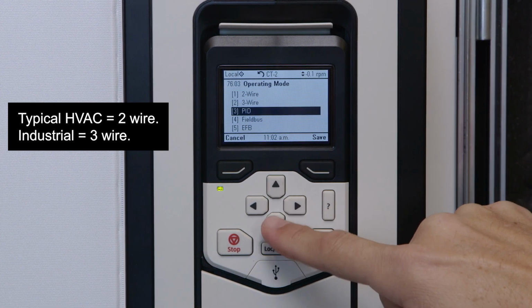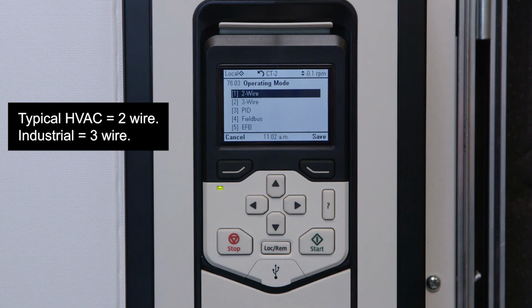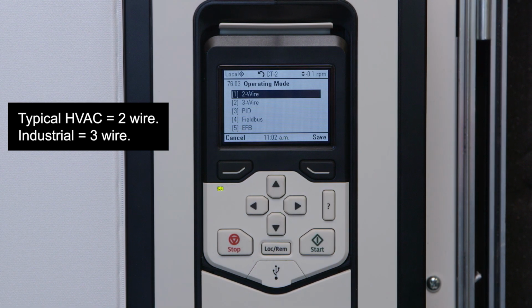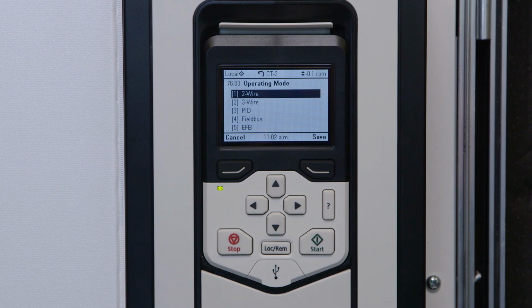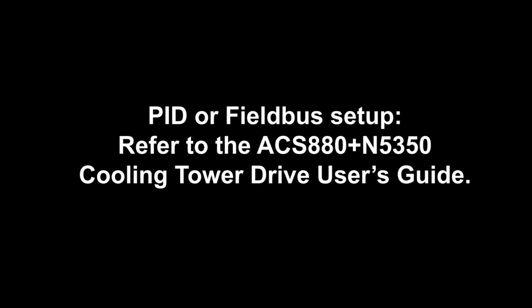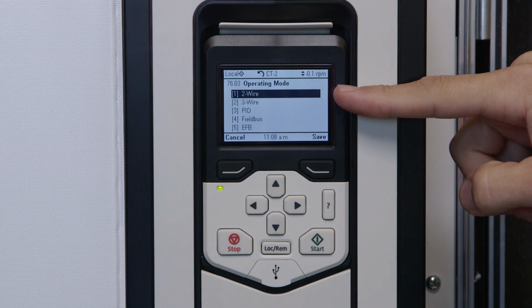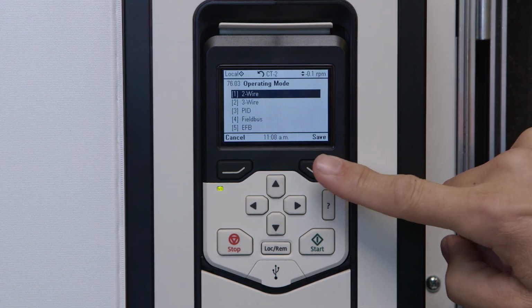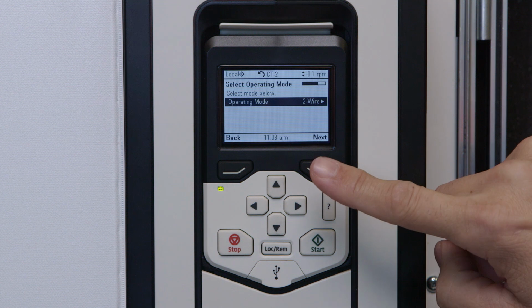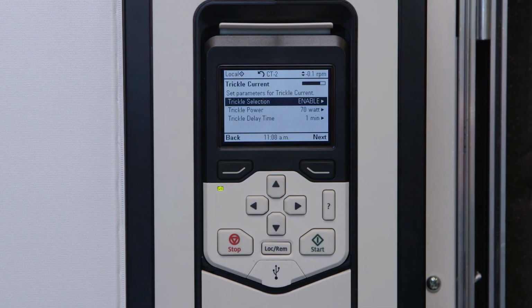The 2-wire BMS start-stop command has leads to terminals XD24-4 and XDI-1. The 3-wire BMS start-stop command has leads to terminals XD24-4, XDI-1 and XDI-2. For PID or field bus setup, see the ACS880 Cooling Tower Drive User's Guide. Select the wiring configuration that corresponds to your BMS start-stop command. Select Save, then press Next.